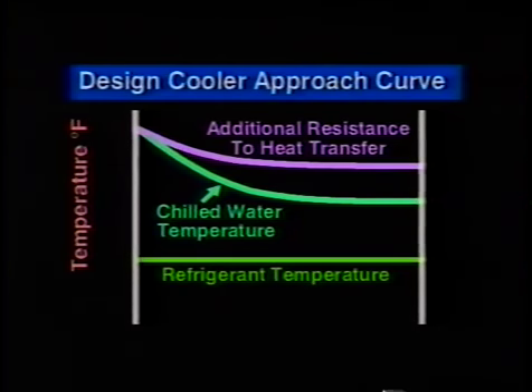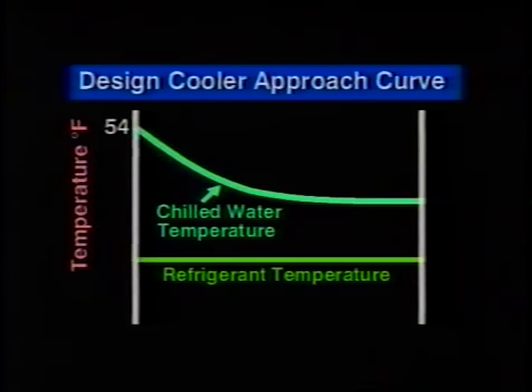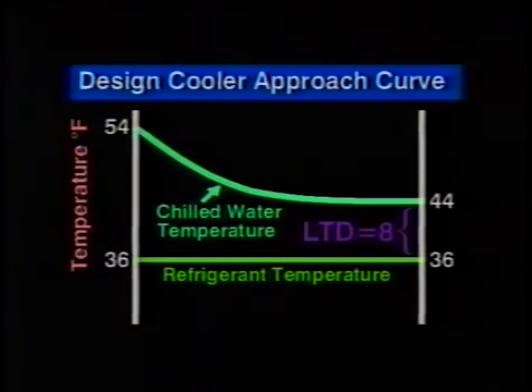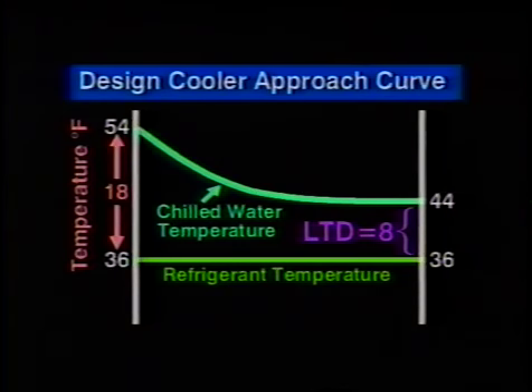In this example, we have 54 degree Fahrenheit entering chilled water and 44 degree Fahrenheit leaving chilled water. The saturated refrigerant temperature is 36 degrees. You can see that the cooler leaving chilled water temperature is 8 degrees higher than the saturated refrigerant temperature, and the entering chilled water temperature is 18 degrees higher than the refrigerant temperature. So, our approach curve will look like this. But remember that this is for full load conditions only. At part load conditions, the 10-degree drop across the cooler will be reduced.